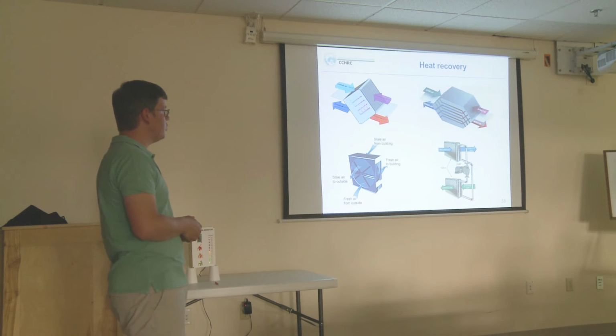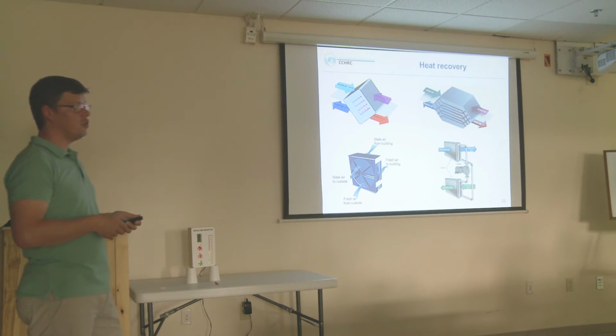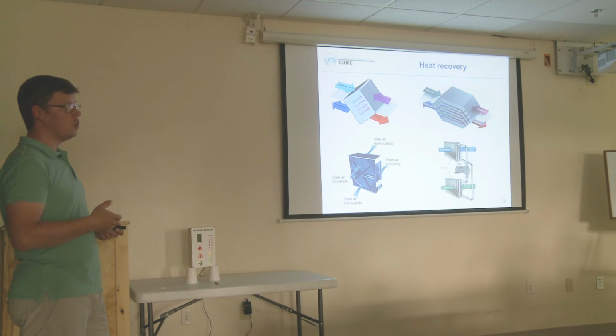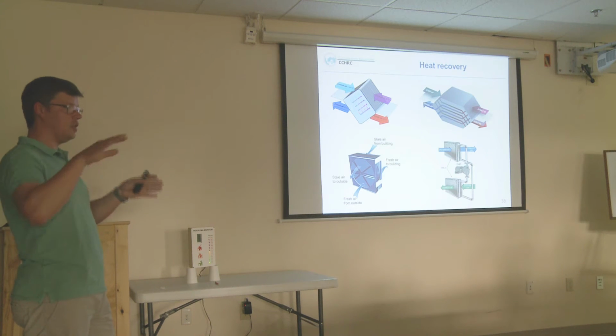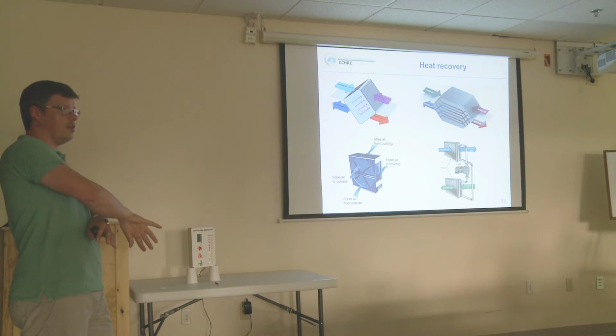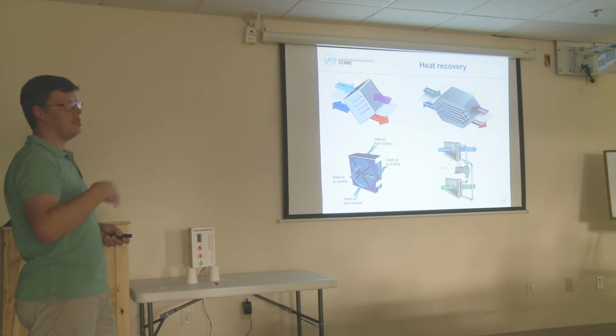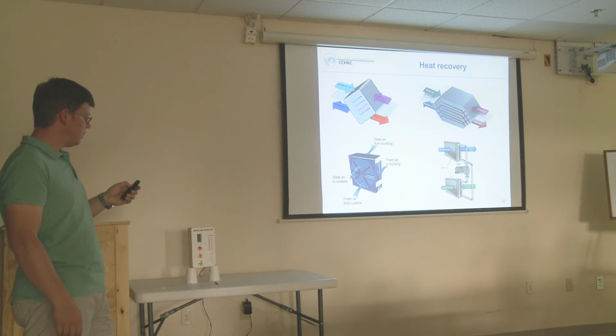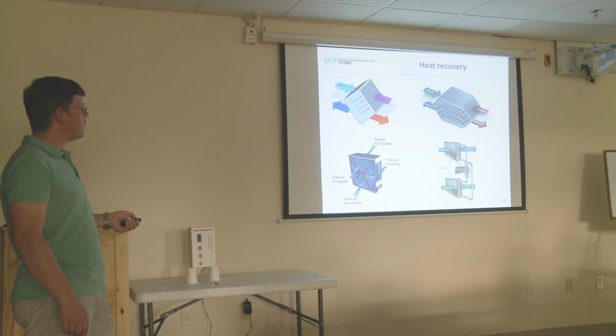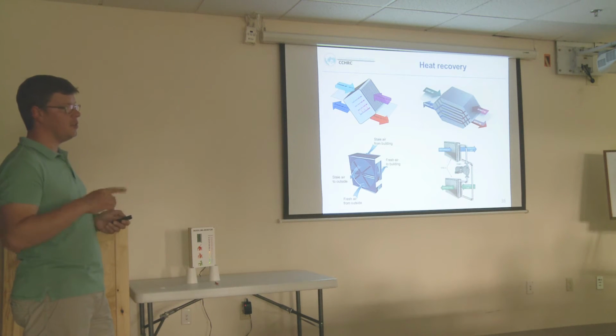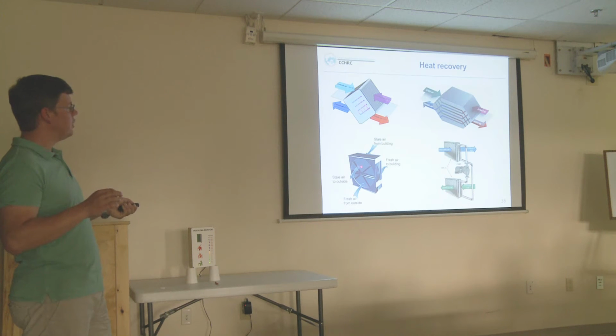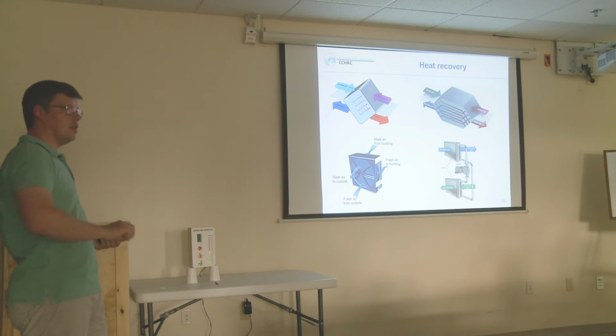This one actually could also have the chambers painted with a desiccant, so they have a very good moisture recovery, because the moisture in the stale air gets absorbed in the walls, and then when it gets to the fresh air, the moisture evaporates back to the supply air. Or even if there is no desiccant on the walls or on the material, there still is a certain moisture recovery, because if there is condensation, the water drops will stay in the chambers and then evaporate as they get down.